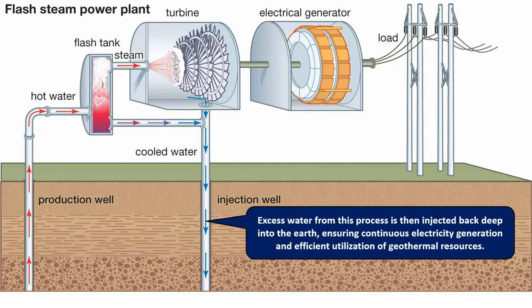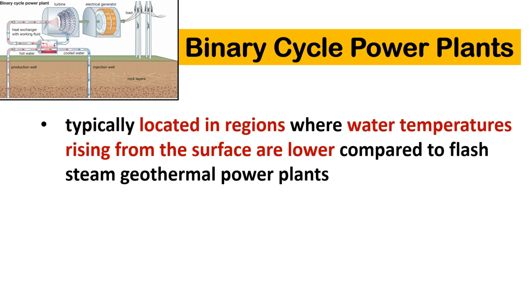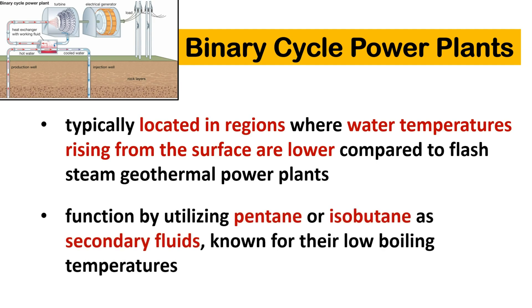Excess water from this process is then injected back deep into the earth, ensuring continuous electricity generation and efficient utilization of geothermal resources. Binary cycle power plants are typically located in regions where water temperatures rising from the surface are lower compared to flash steam geothermal power plants. They function by utilizing pentane or isobutane as secondary fluids, known for their low boiling temperatures.